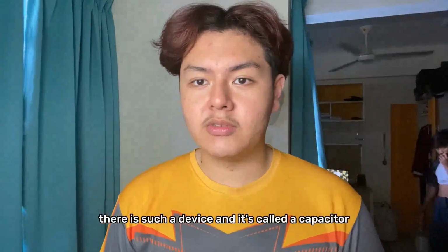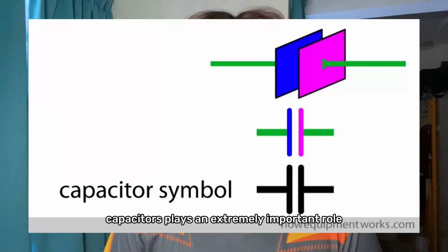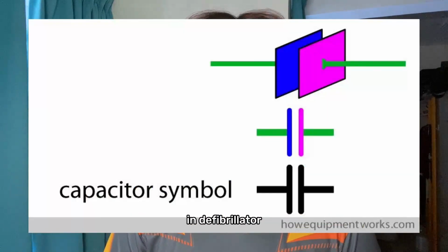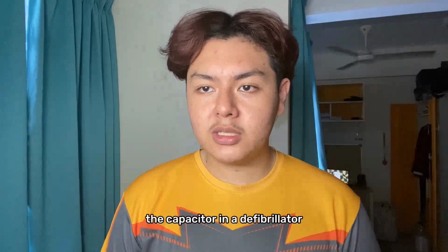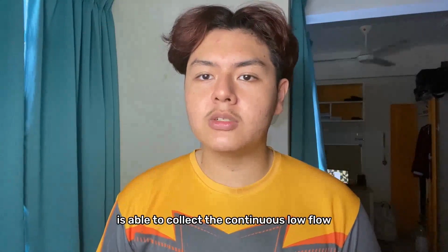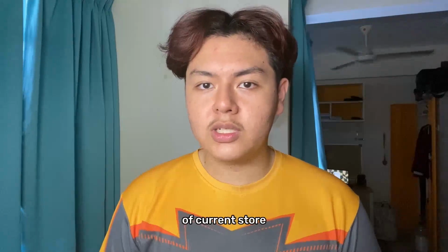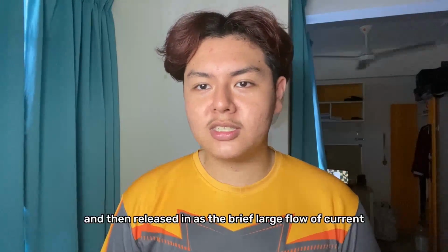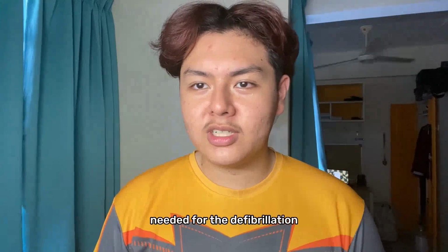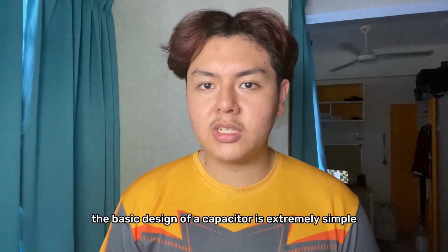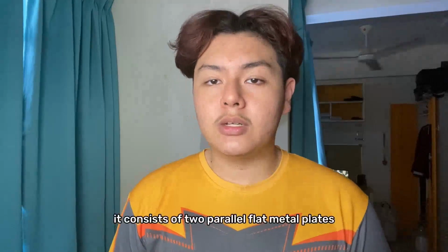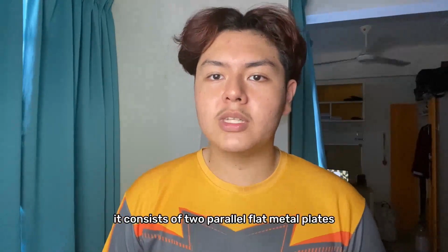Fortunately, there is such a device and it's called a capacitor. Capacitors play an extremely important role in defibrillators. The capacitor in a defibrillator is able to collect the continuous low flow of current, store what is collected, and then release it as the brief large flow current needed for defibrillation. The basic design of a capacitor is extremely simple. It consists of two parallel flat metal plates.